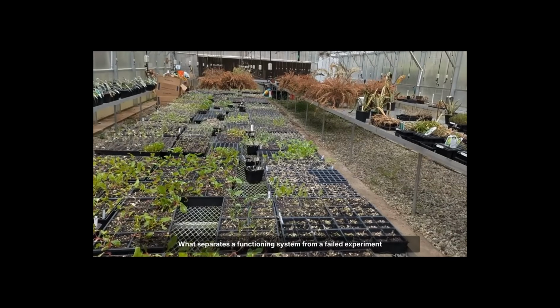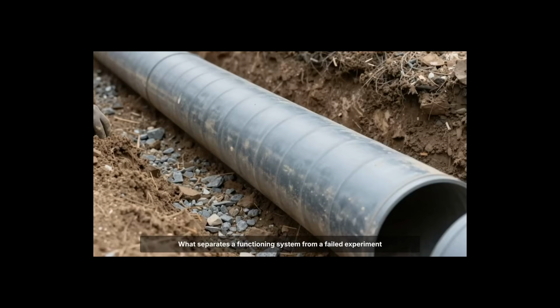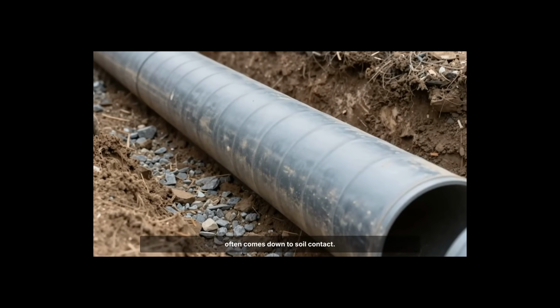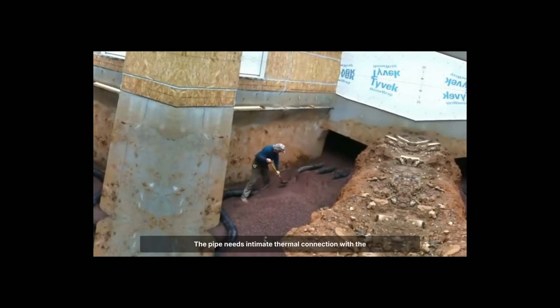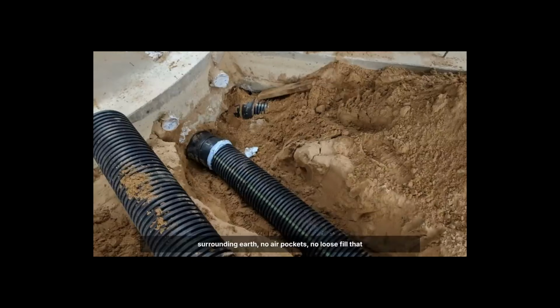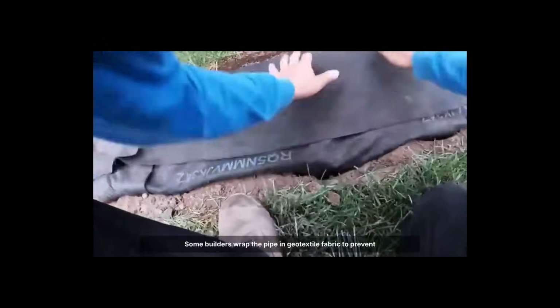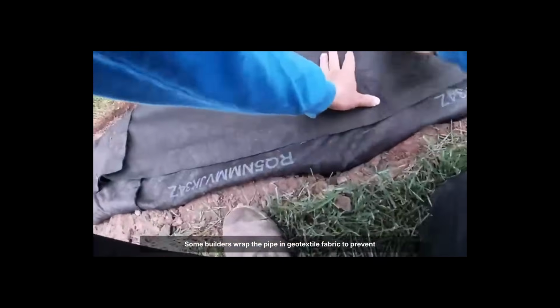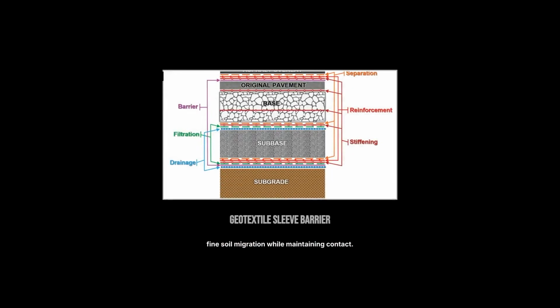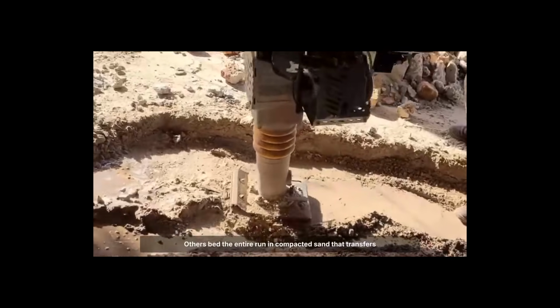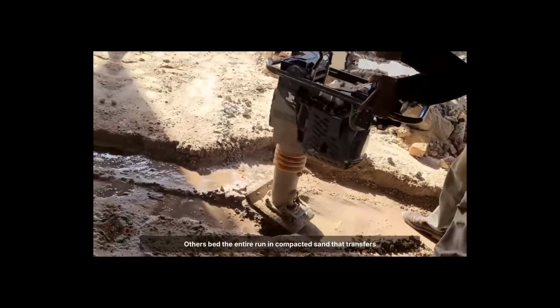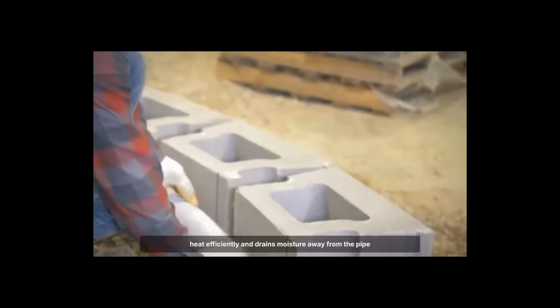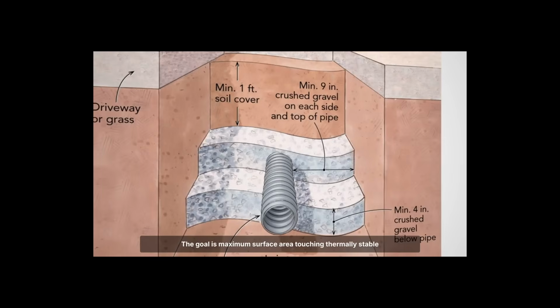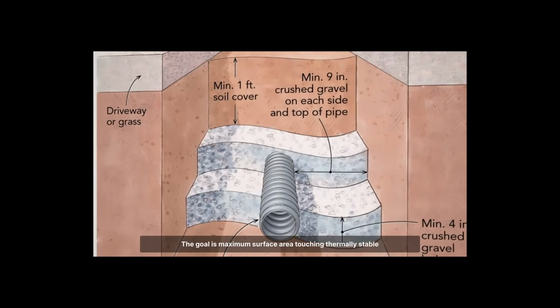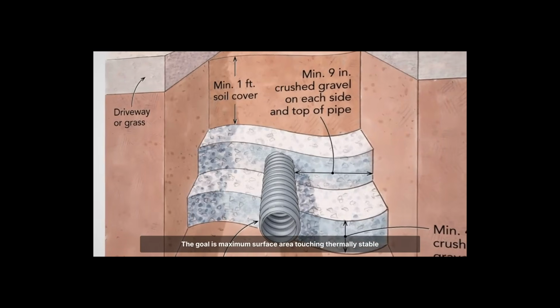What separates a functioning system from a failed experiment often comes down to soil contact. The pipe needs intimate thermal connection with the surrounding earth. No air pockets, no loose fill that settles into voids over time. Some builders wrap the pipe in geotextile fabric to prevent fine soil migration while maintaining contact. Others bed the entire run in compacted sand that transfers heat efficiently and drains moisture away from the pipe surface. The goal is maximum surface area touching thermally stable mass.